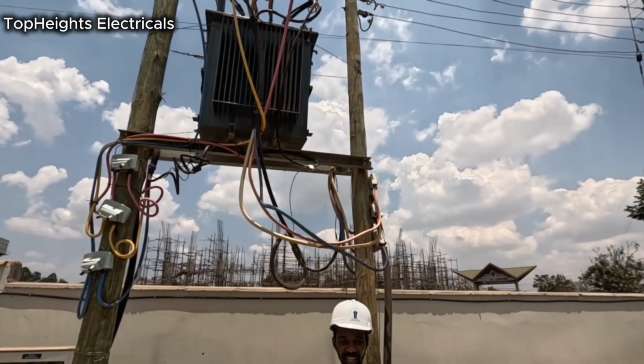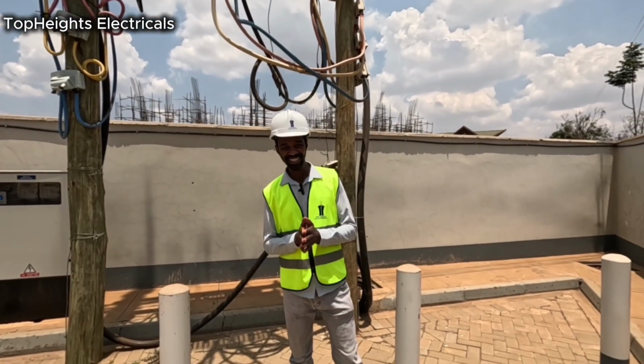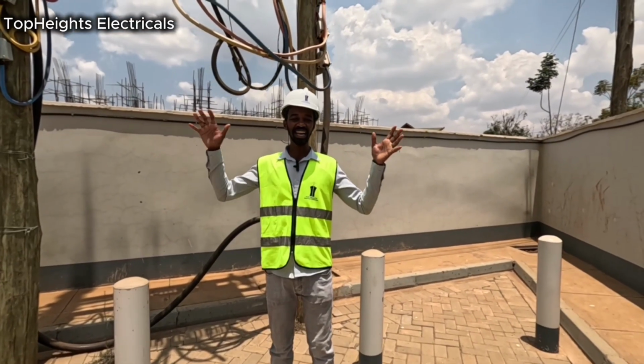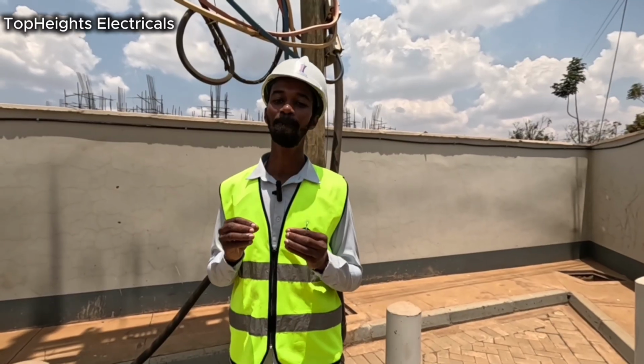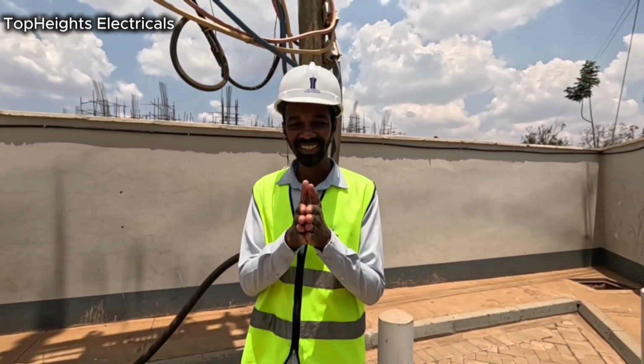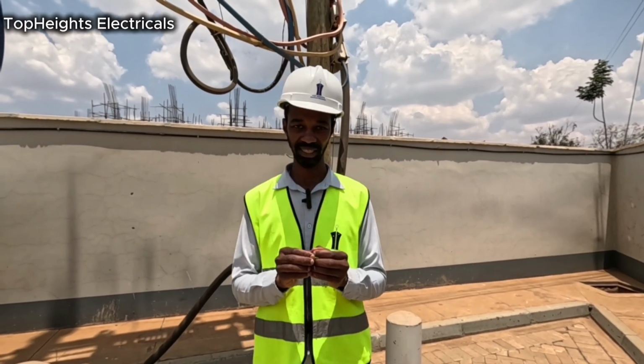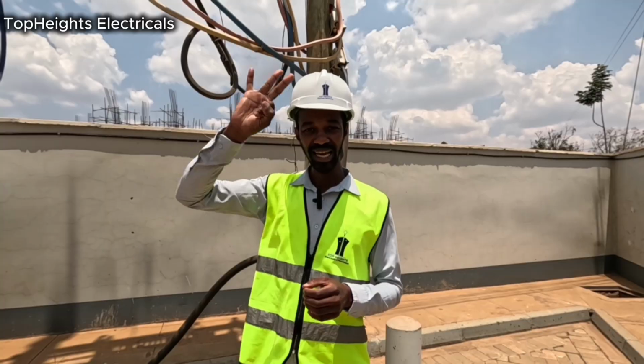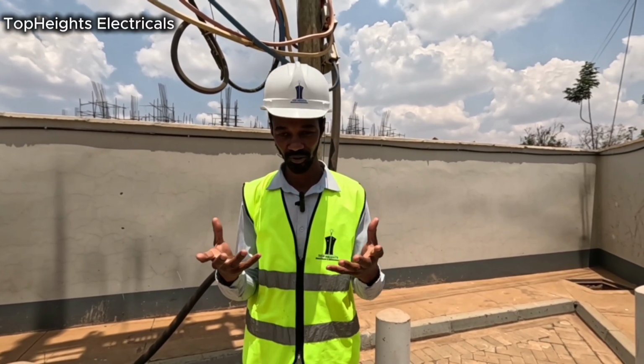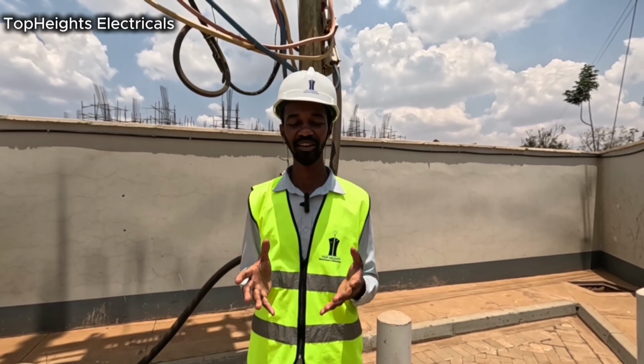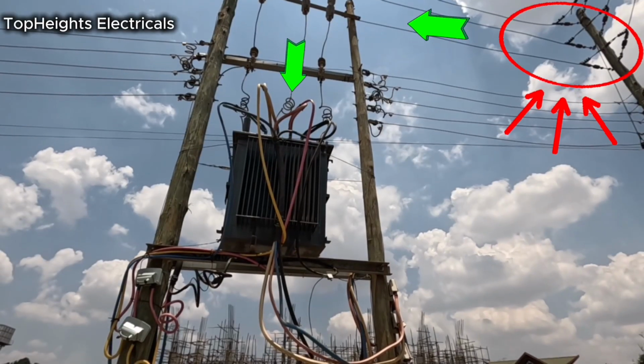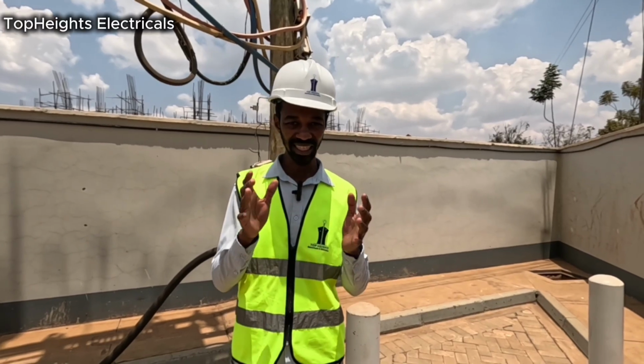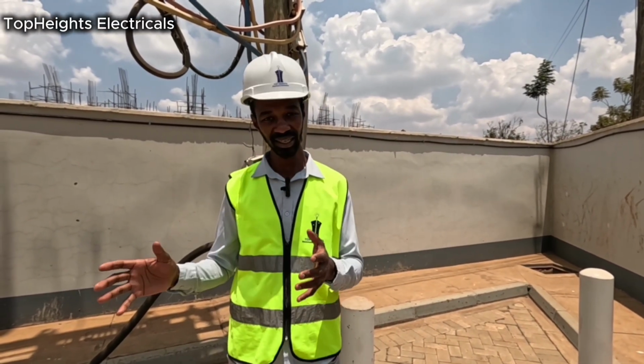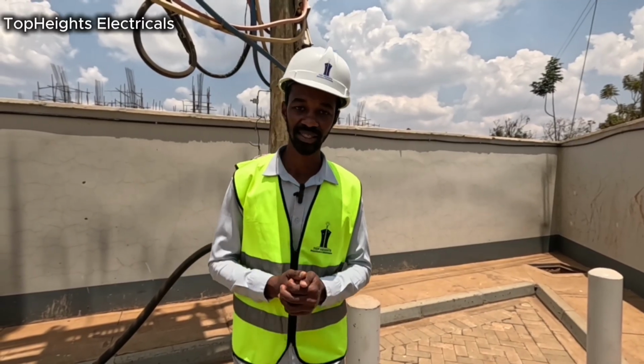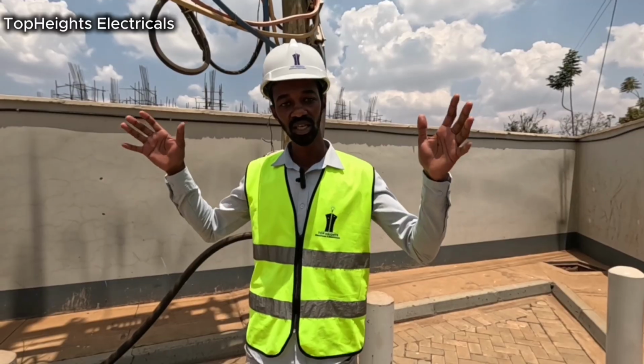Did you know that for an electric vehicle charging station, power is harnessed from the national grid? This is an incredible charging station courtesy of Basigo here in Kenya. To make it simple, we have 11,000 volts coming all the way from the national grid. The three conductors feed and energize the transformer, carrying 11,000 volts, or 11 kV. These feed the transformer, stepping down the voltage from 11,000 volts to a three-phase low voltage power line of 415 volts, which is of course AC. This is what is fed to this EV charging station.